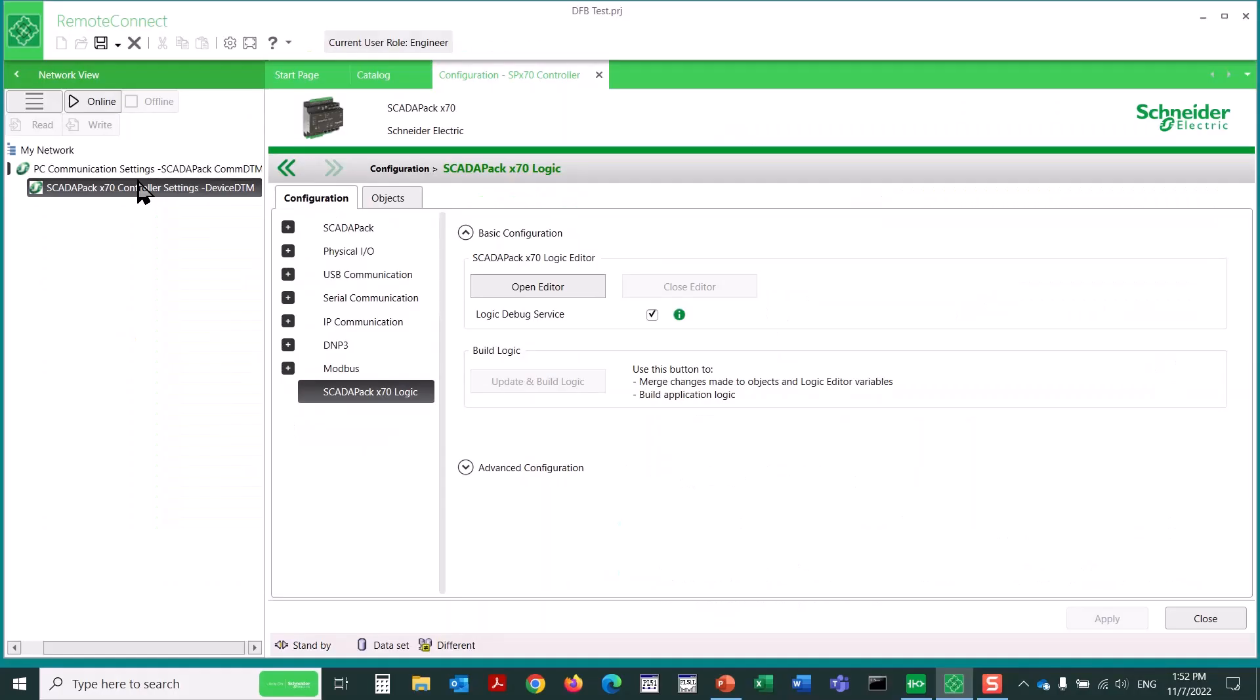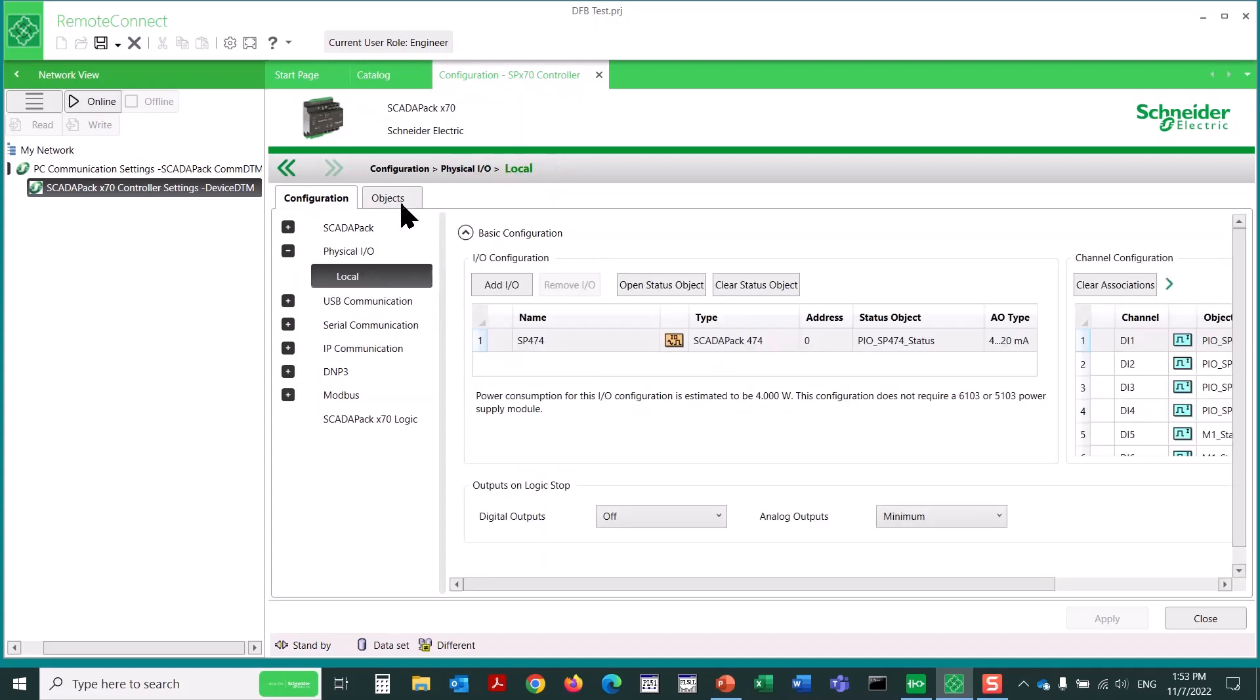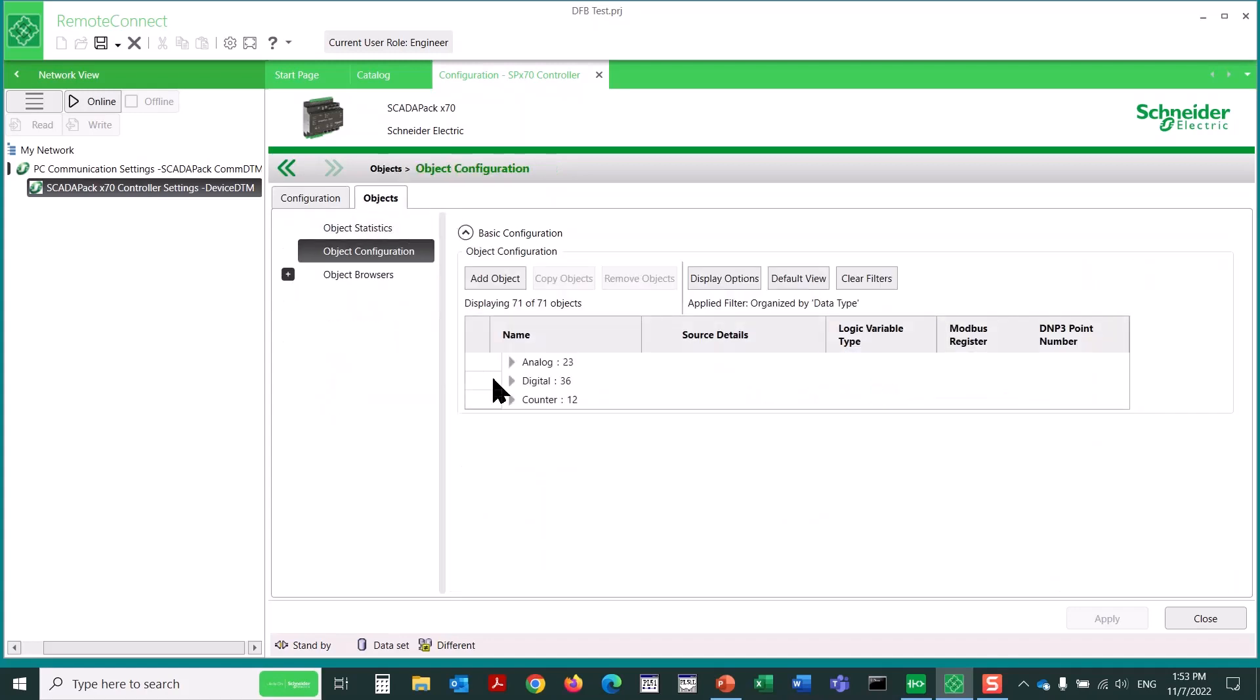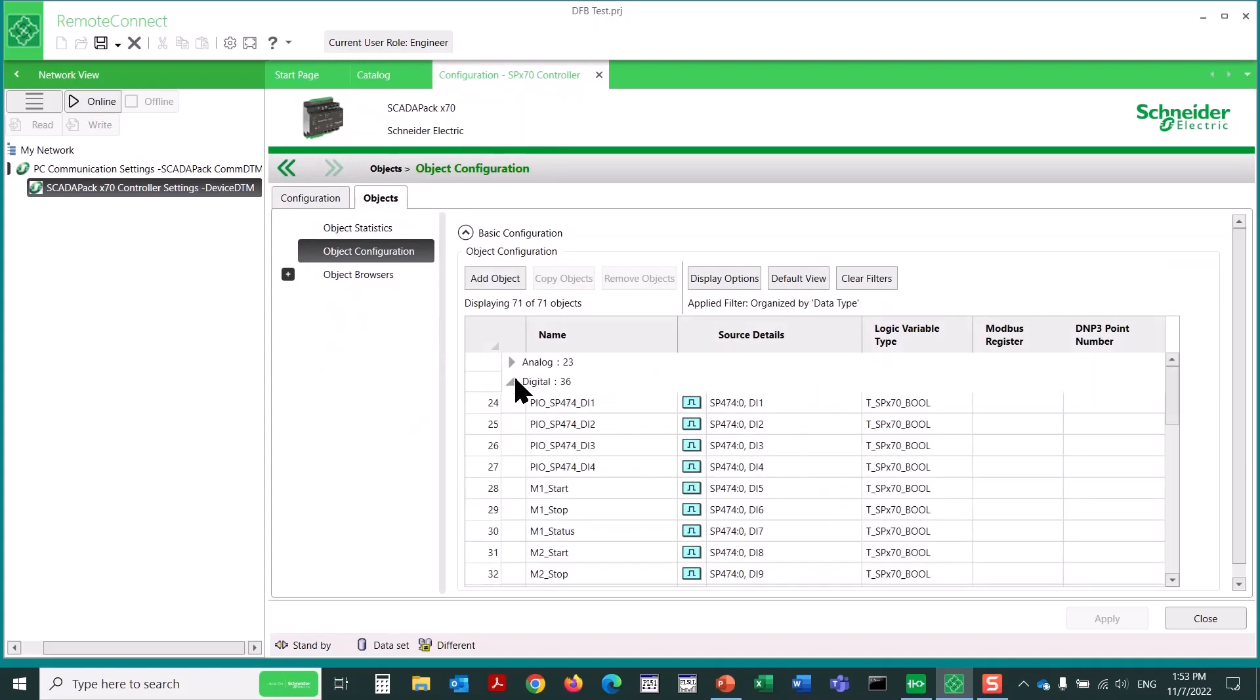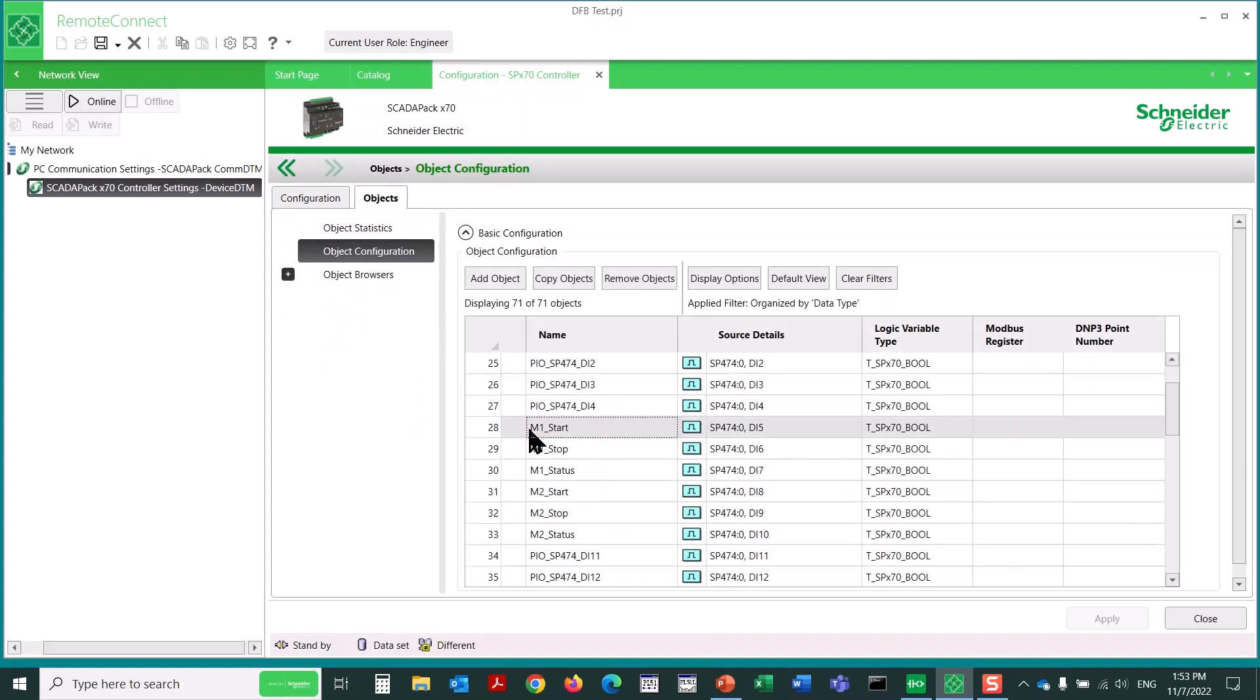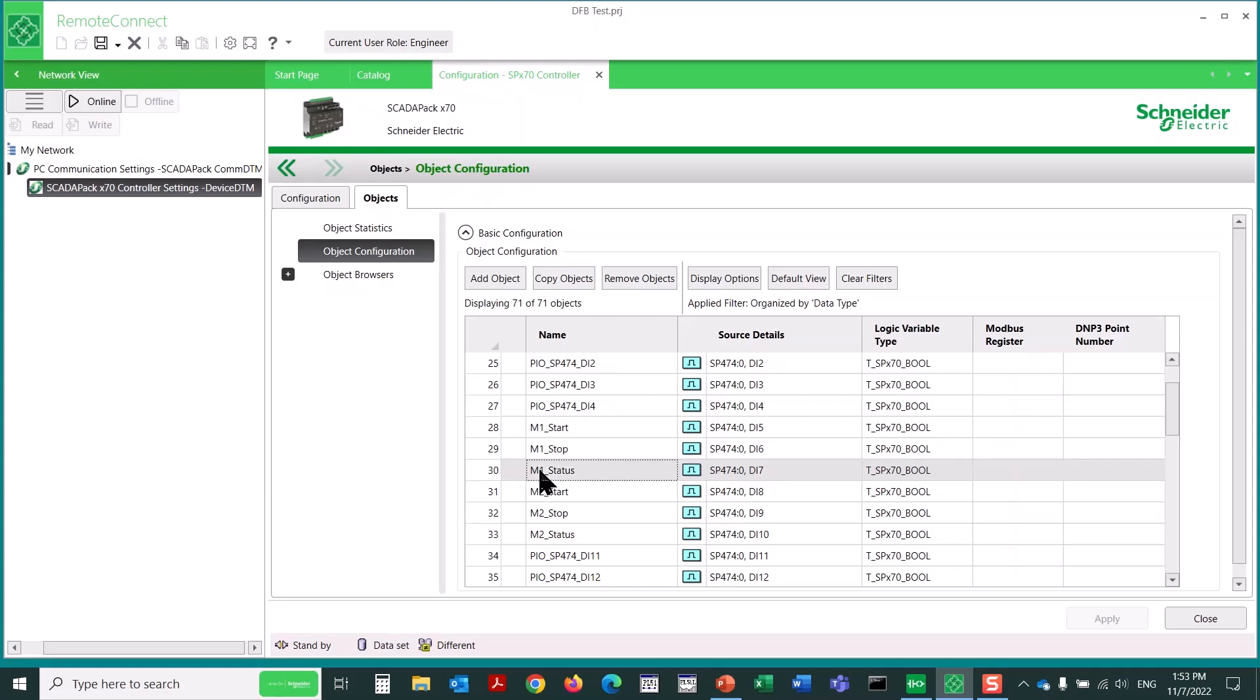Now let's have a look at the process of creating and using a derived function block in the RemoteConnect Logic Editor. I'll create a DFB that'll help control and monitor multiple motors. In the digital area of the objects tab, I've already renamed several digital inputs. We can see digital input 5 is M1 start, 6 is M1 stop, 7 is M1 status. These are wired to a physical input simulator board.